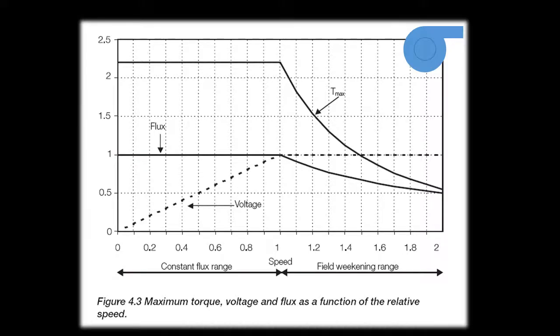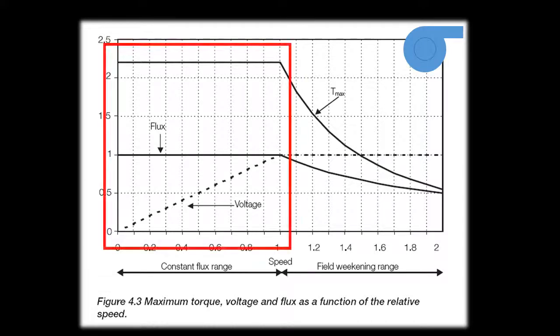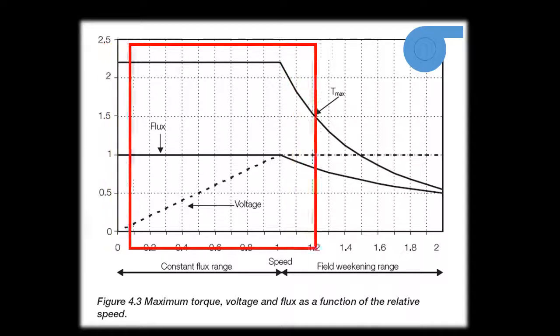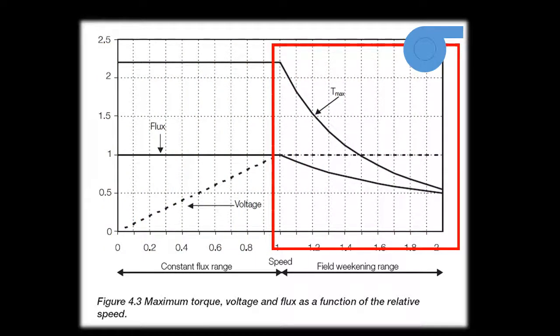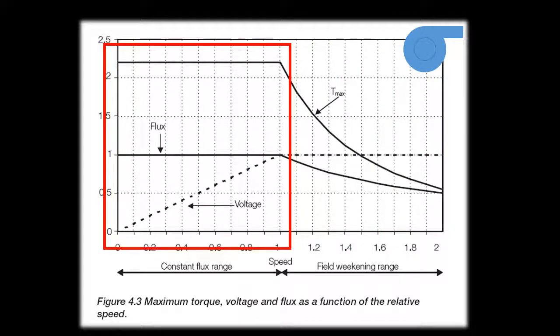A motor's torque-speed relationship can be broken into two defined regions. The constant flux range, seen here as the flat regions of torque and flux, and the field weakening region, seen here with the torque and flux decaying away. In the constant flux range, a constant torque can be maintained by keeping the voltage frequency ratio constant, according to the previous equation. Using a motor in this region can provide a process with VSD motor control while maintaining a constant torque.